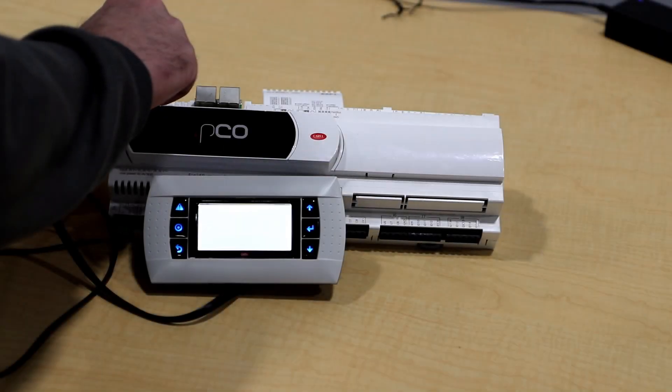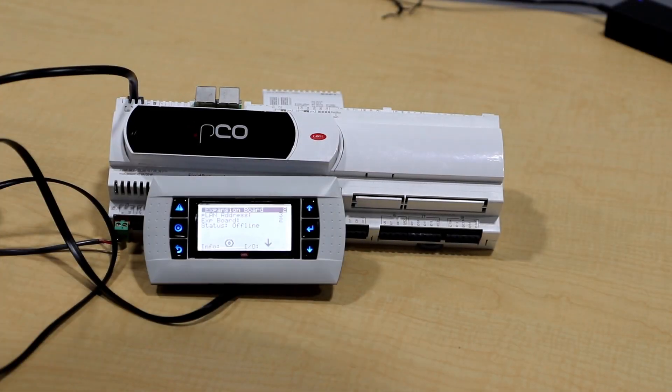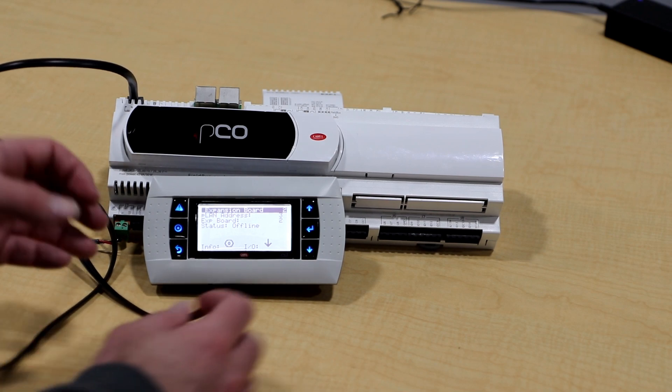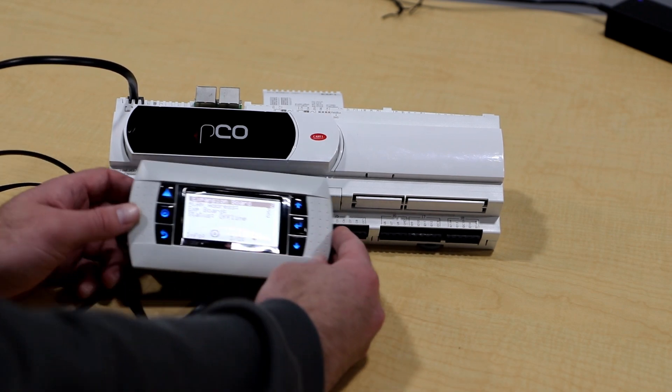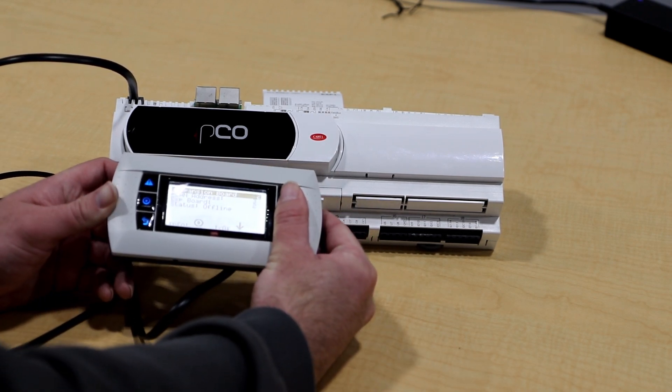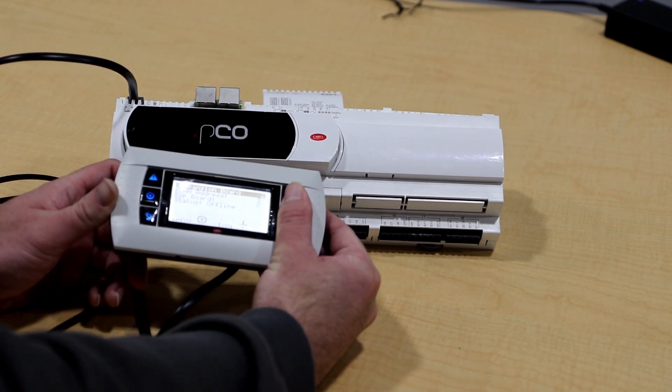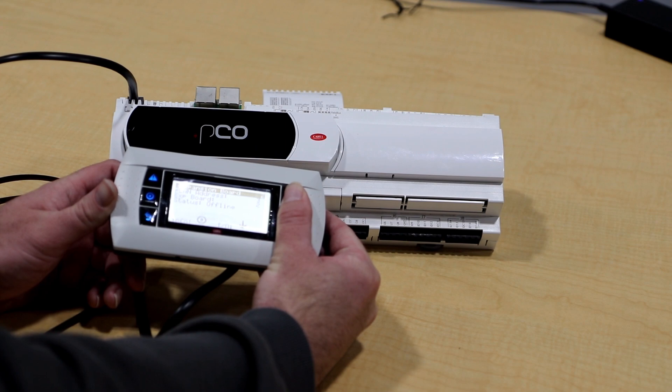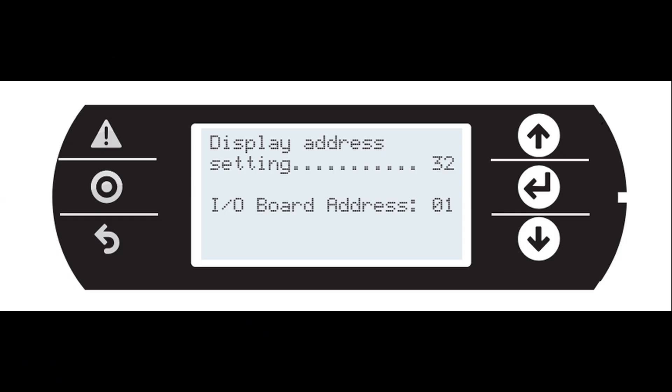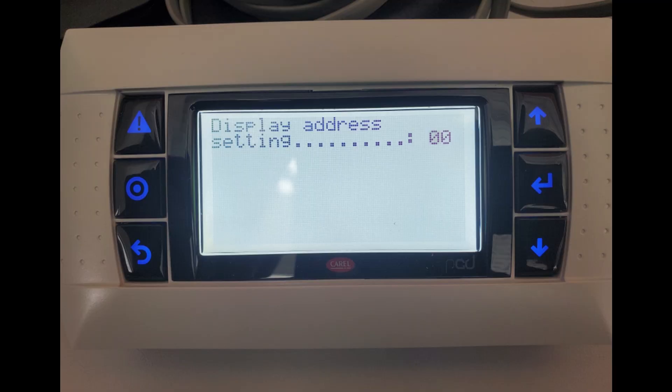Plug in the display and hold the three buttons on the right side. Change the display address to 32 and press enter. If the screen does not come online, reset power on the controller and try again. If the screen is still not displaying, enter 00 for the display address and press enter.